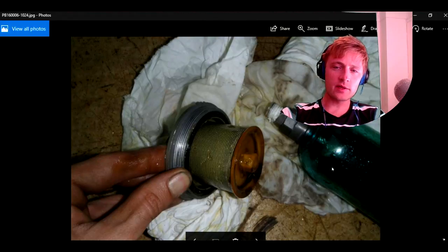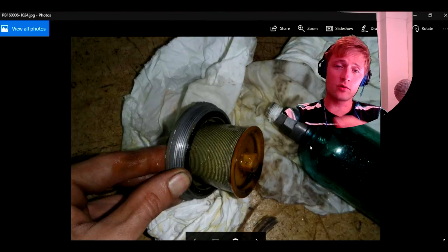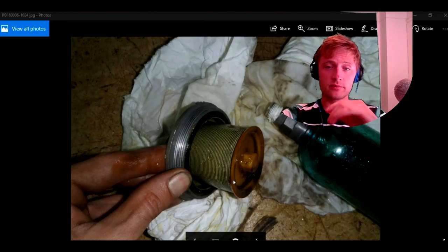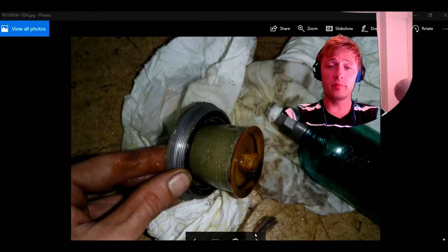These filters — sometimes this glass is breaking from the pressure and also the vibration. Also this filter, it is possible to become blocked, so this also needs to be checked. Over time, these plastics — everything — will break and become worn.